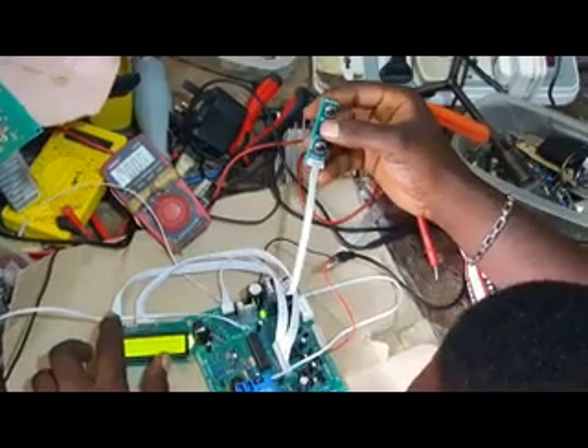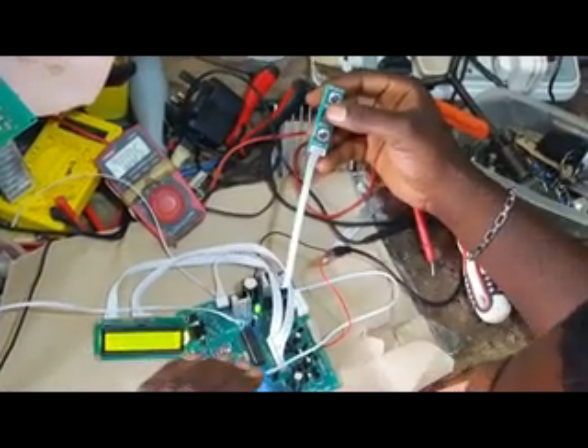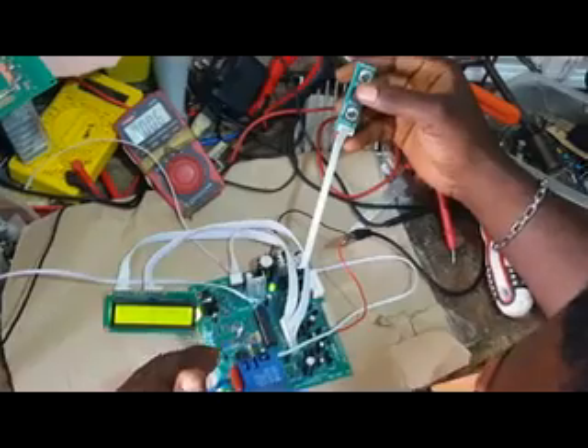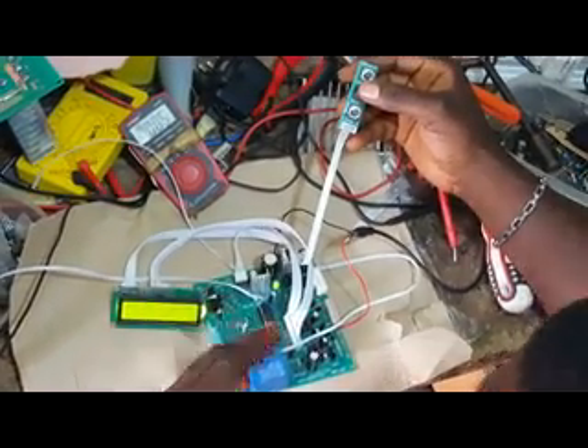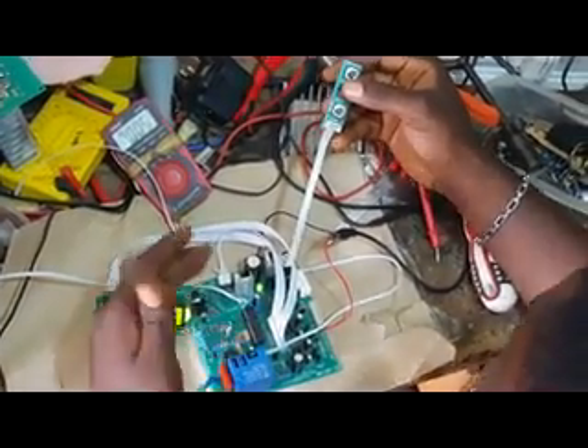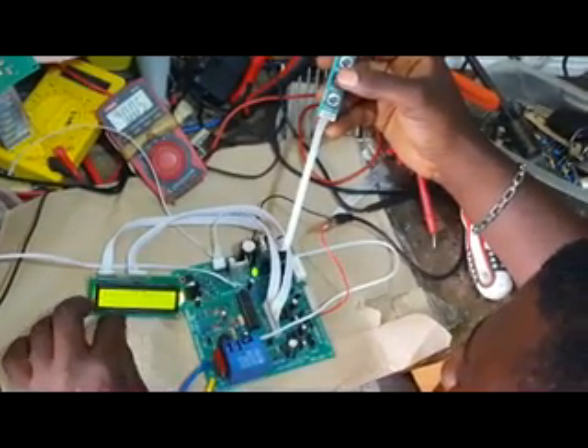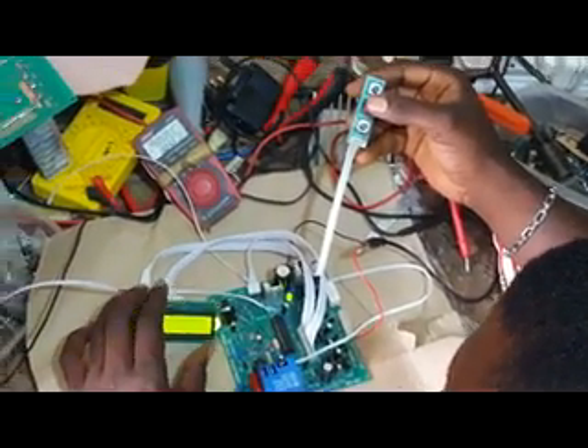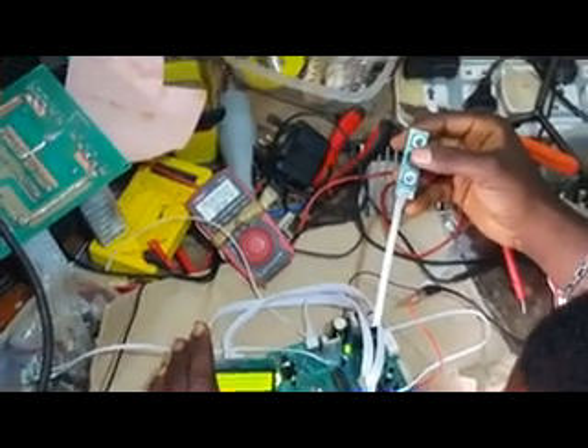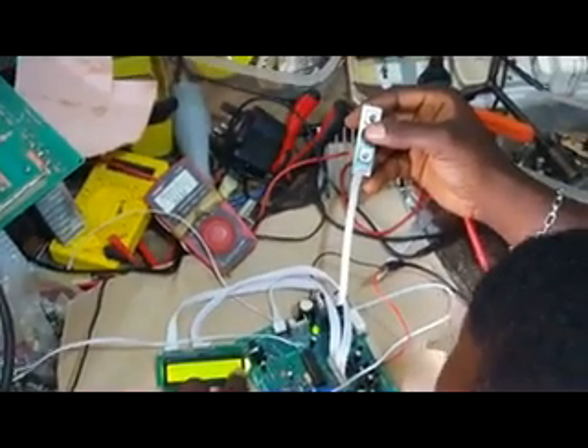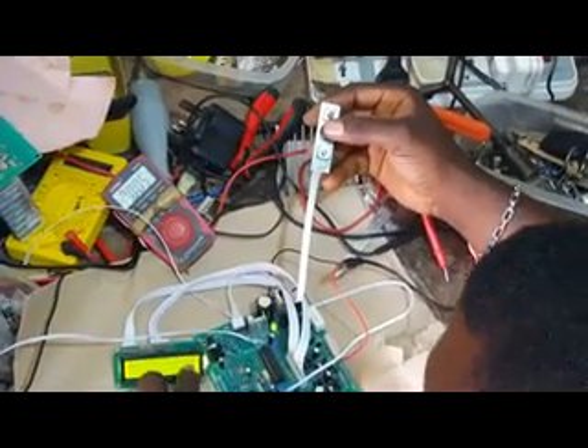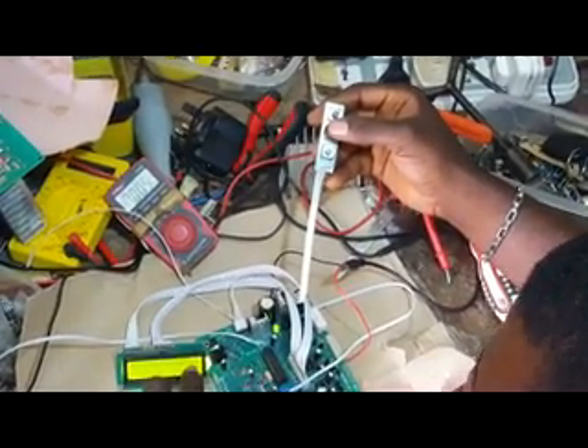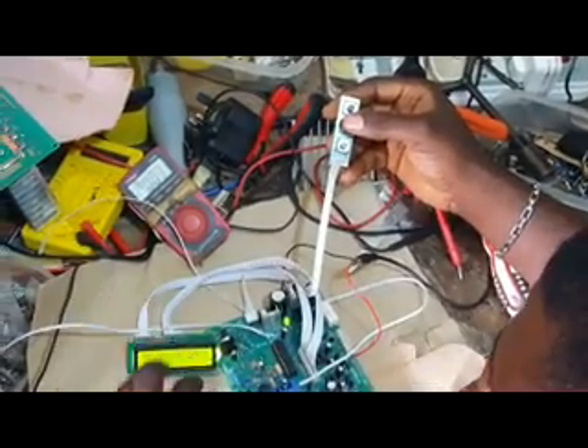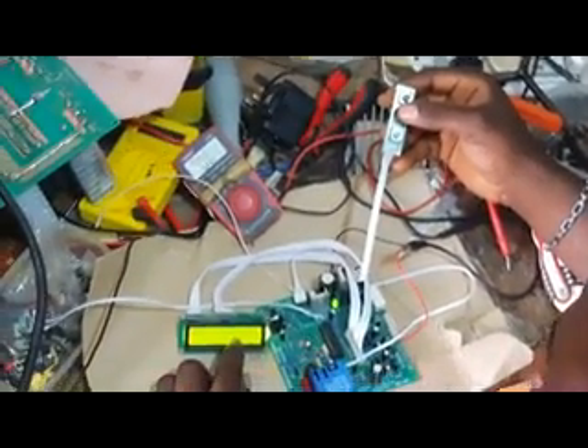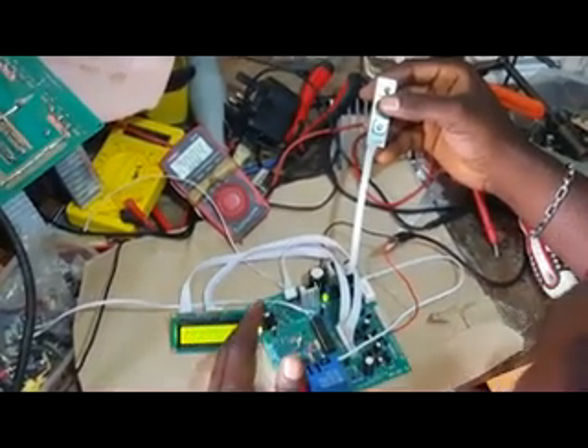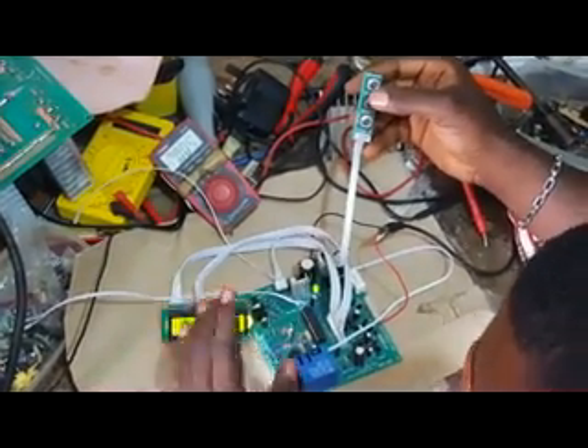My absorb mode - there's a bulk charge and a floating charge, or absorb charging and bulk charging. The inverter board is going to charge the battery up to 13.8 with the full charging amps, then start reducing the charging amps gradually until the battery gets full. So your absorb charging resumes after 13.8. That's it for that.